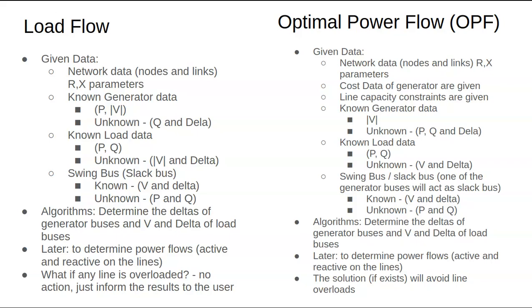Now what is your response? How can I meet that load, based on historical data? If you see what the peak is, let's say the peak is 400 kilowatts. Then you will see how many generators I have. Let's say you have only two generators. One generator is 100, the other generator is 300. So 400 exactly matching, fine.